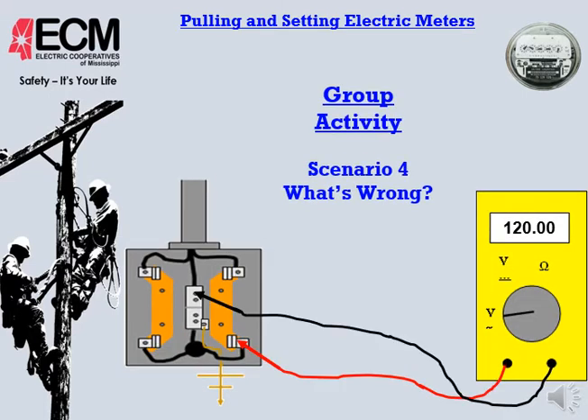And again, same problem here. We've got some stray voltage coming from a source that we're not sure of. And we do know in this position we shouldn't get any voltage reading at all. And the main thing is we stop at this point. We don't set the meter.